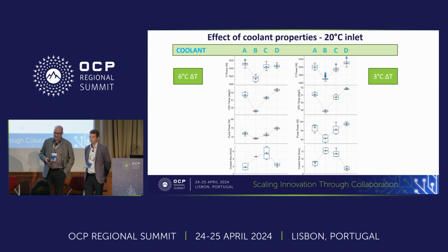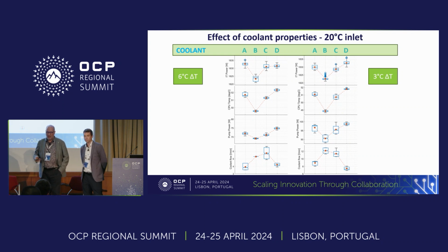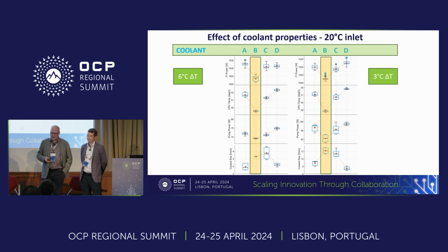But we actually did the whole thing at different temperatures. We looked at the high and the low end, so the 20 degrees centigrade here, and you can probably guess what's causing this, why this fluid B, this coolant B, is doing so well. But again, one of the things I should point to here is the CPU temperature. The CPU temperature now is down in the 50s, and that's because our inlet temperature is now 20 degrees. And because the inlet temperature is 20 degrees, you can see the power draw of the IT changes. There are no fans in it. It's all the microelectronics drawing more power, or less power in this case, because we're running at a lower temperature.